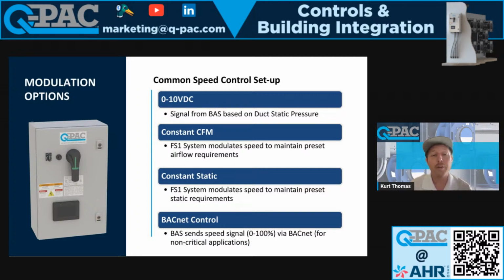Constant CFM. If you have an application where you need to ensure that a certain amount of air is moving, then we can do that. You don't need to connect it to your BAS. You can type into the HMI or via BACnet and say, hey, I need you to run or move this much air, and we will ramp the fans up and down to maintain that. You will, however, need to calibrate your PID constants. So you want to make sure that your fans aren't ramping up too fast or too slow, and whenever they hit the set point, that they are running at a stable speed and not overshooting and undershooting, right?